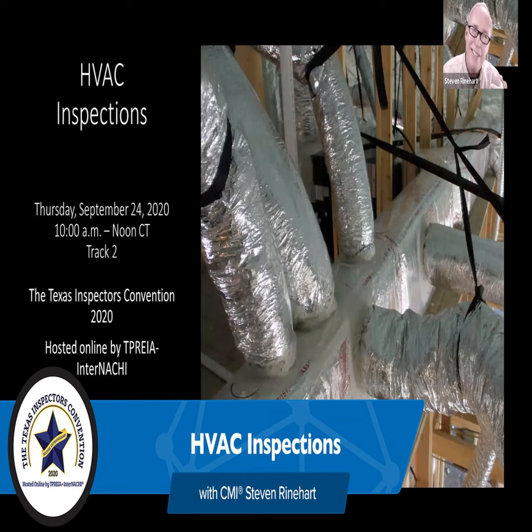Worst case is somebody stubs it into the return plenum, sticks the other end out through the roof, and there's no damper, no filter. That's an air leak. And you're just pulling in air from outside, unfiltered, uncontrolled. Can't turn it off. It's kind of like every time you get in your truck and turn on the ignition, the window comes down, with the intent of giving you fresh air, whether you want it or not. No, you've got to control it. There's the filter and there's a controller. So if it's there, you need to have all the parts.